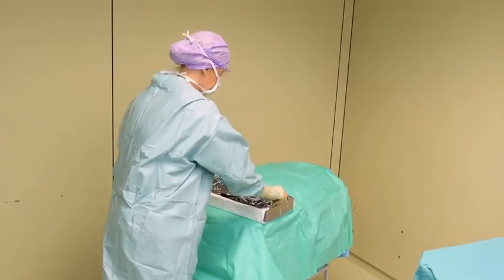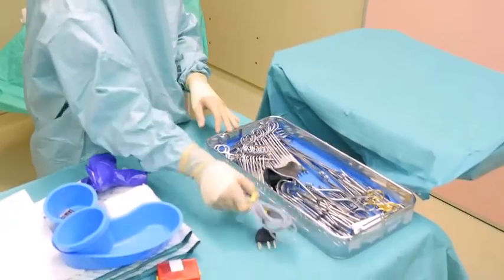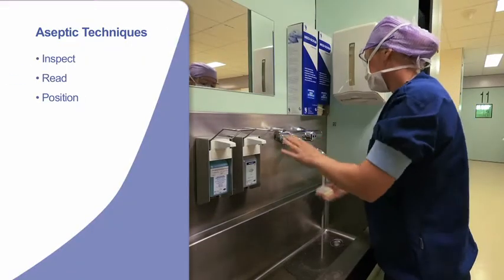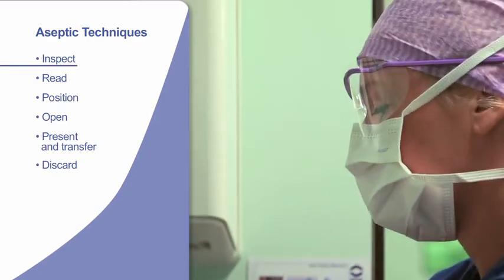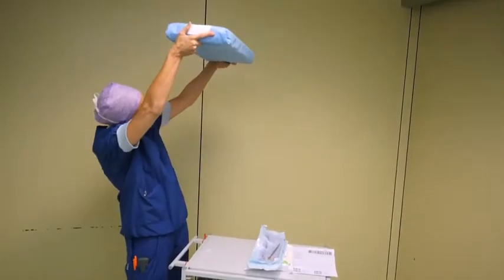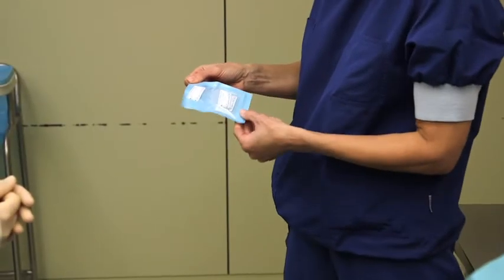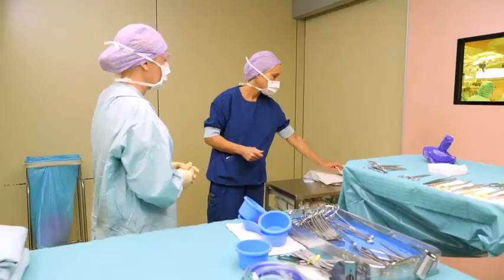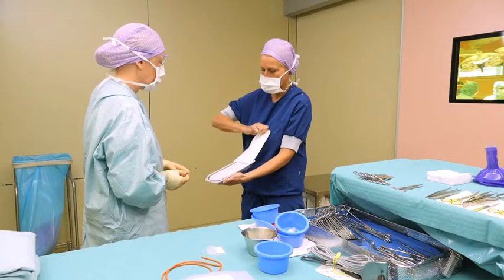Movement should be minimized and the activity should take place in an appropriately controlled environment. Ensure the integrity of the barrier system by looking for any potential damage, for example tears and punctures, open channels in the seals or seal failures. Consider the stress put on parts of the pack by the device. Preformed and semi-rigid trays should be free of dents, cracks or splits. If packaging is damaged, do not use the product and report it.